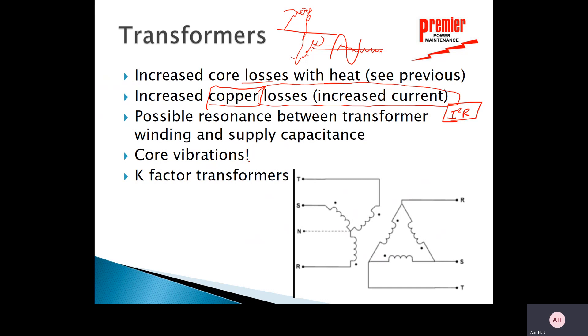A third transformer issue is that resonance can build up between the transformer winding and the capacitance of the system. When we reach the resonant frequency — one over two pi times the square root of LC — we can have unbelievable current flowing in this tank circuit. Core vibrations can also try to dislodge the blocking inside the transformer due to the additional harmonic vibrations.